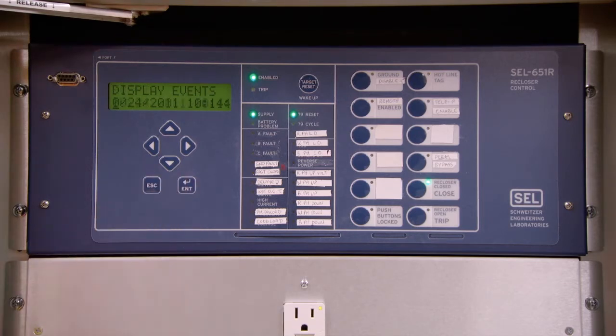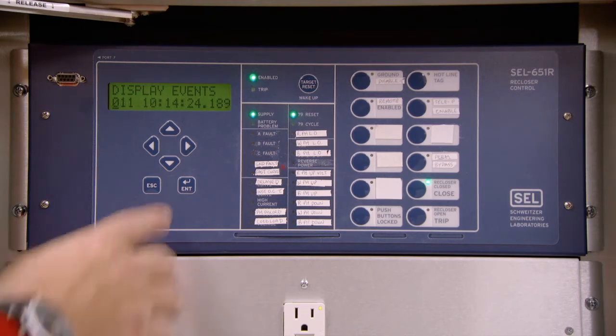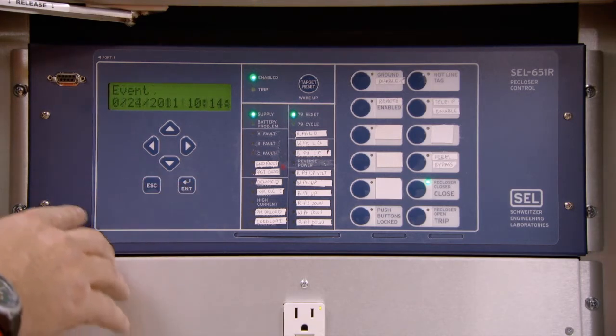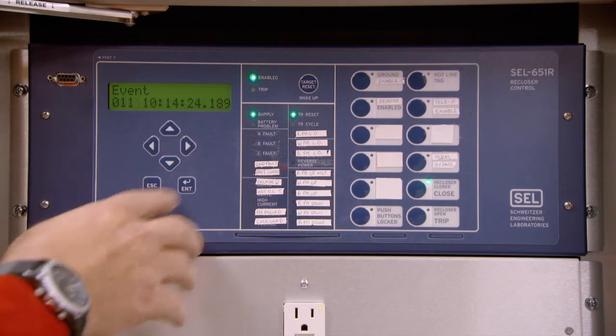Pressing Enter again, the screen will give you the date and time of the last event. The system can have 50 events stored in the log. When those events fill up, the log will rewrite from top down. In other words, the most recent event will be the first one that displays. Pressing the Enter button again will allow you to scroll through the events using the up and down arrow keys.